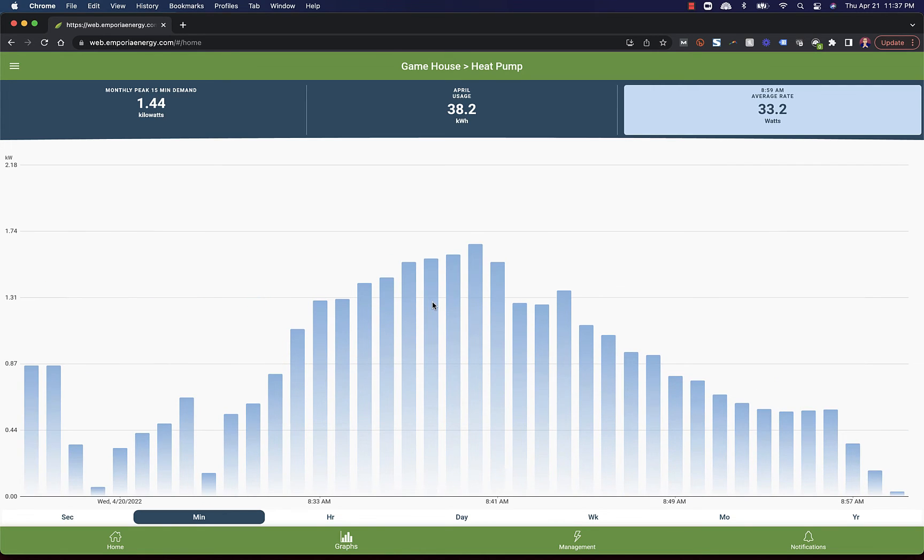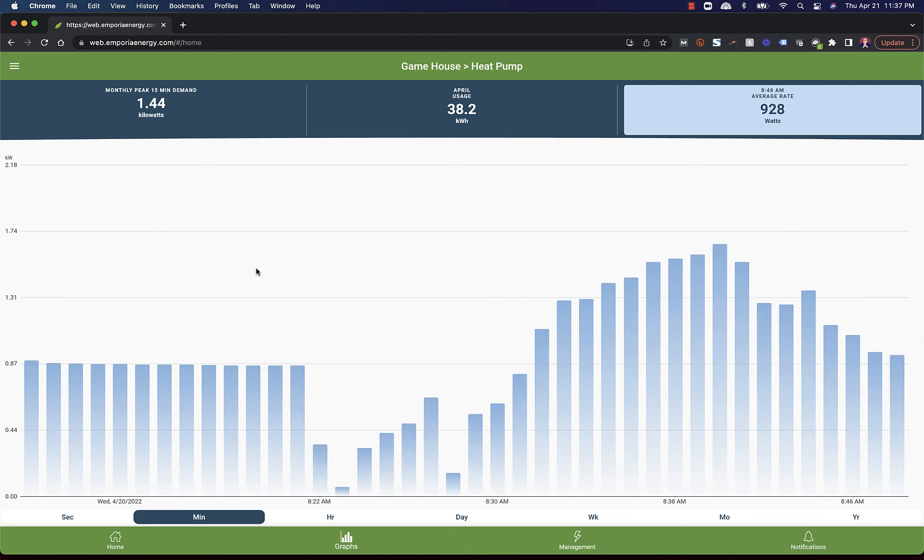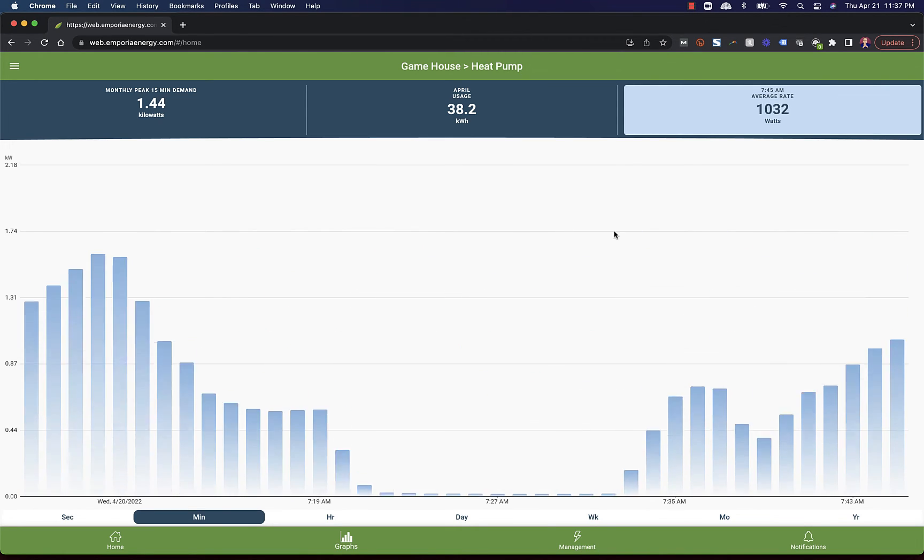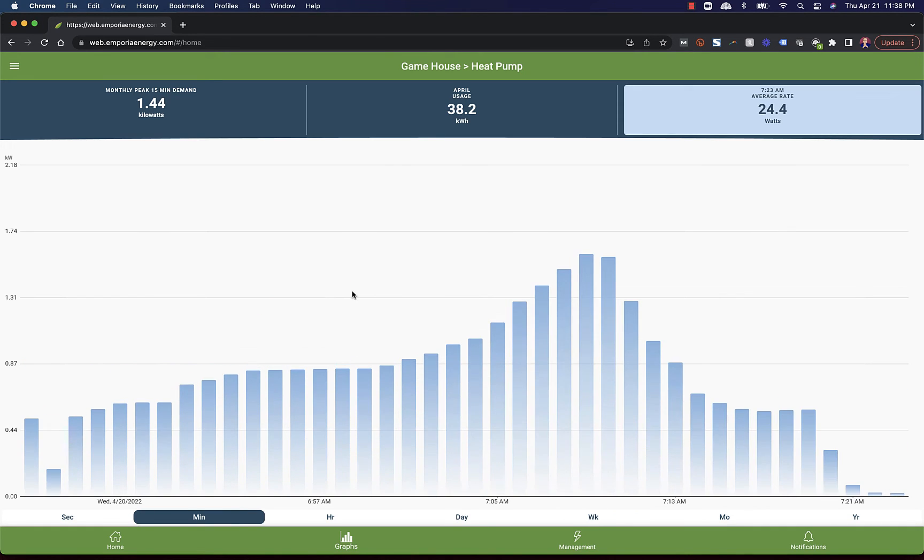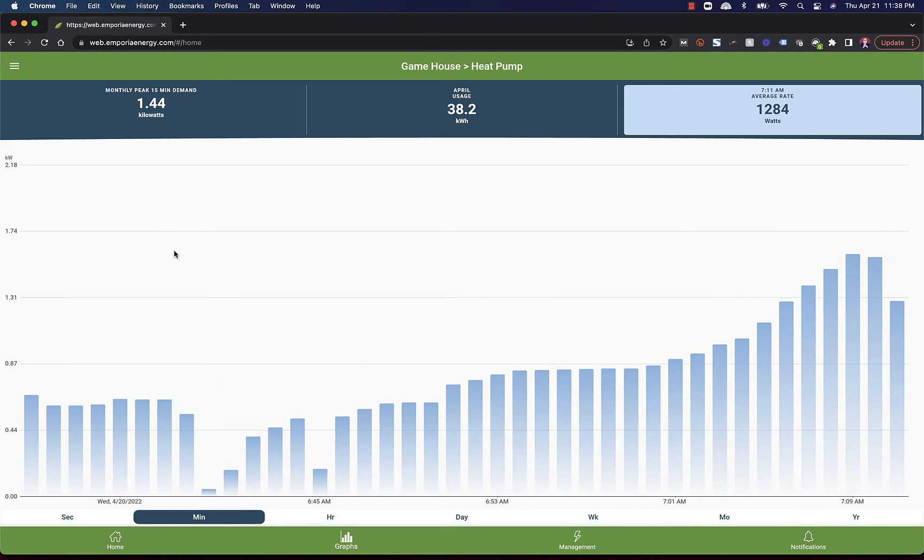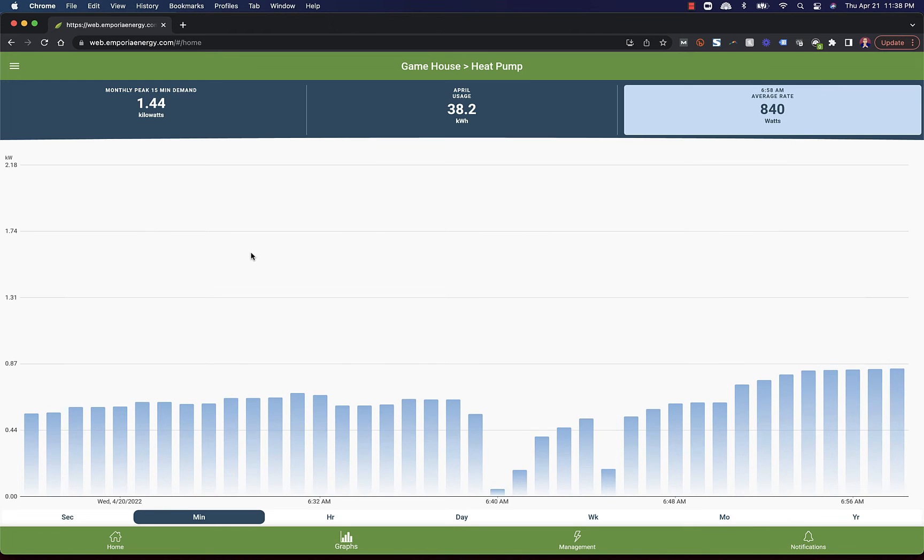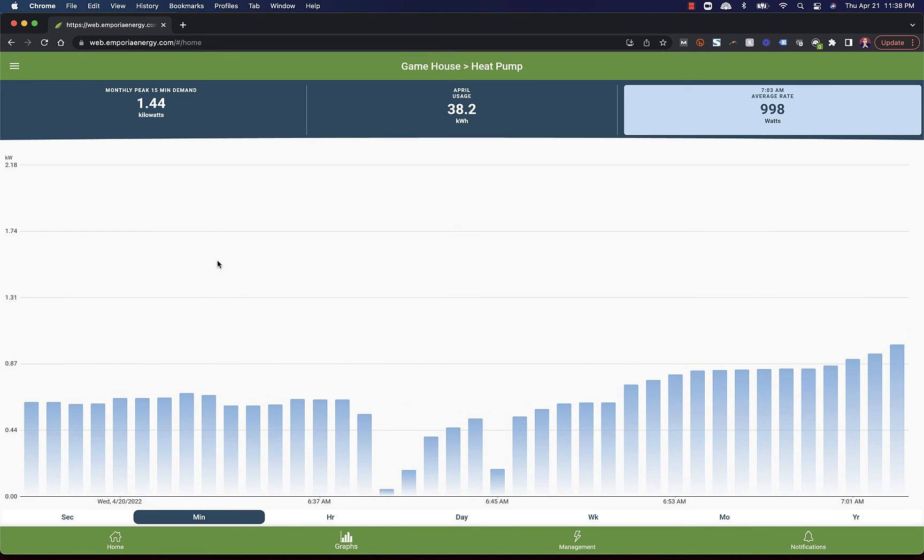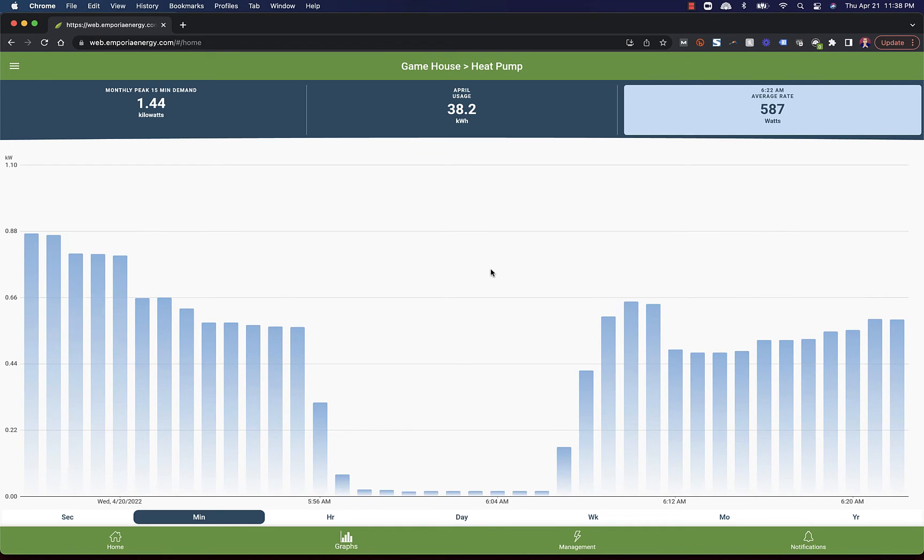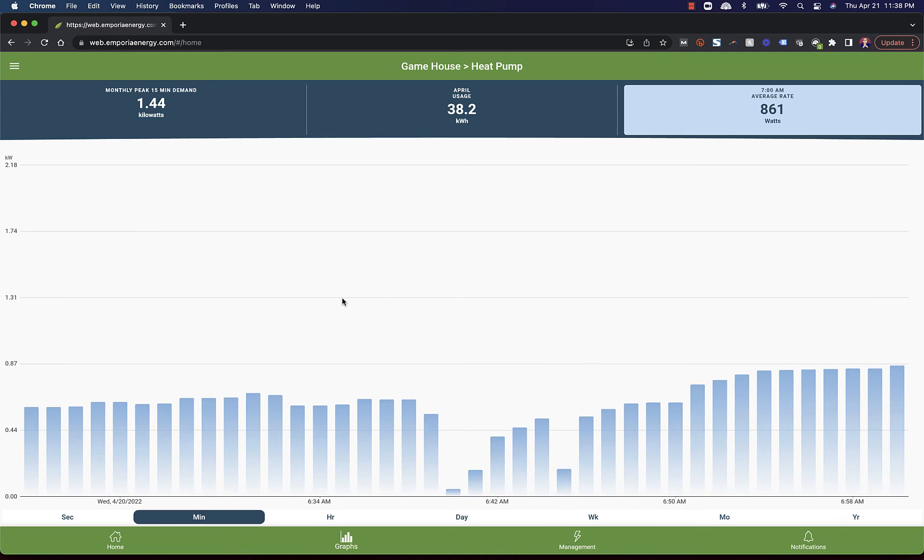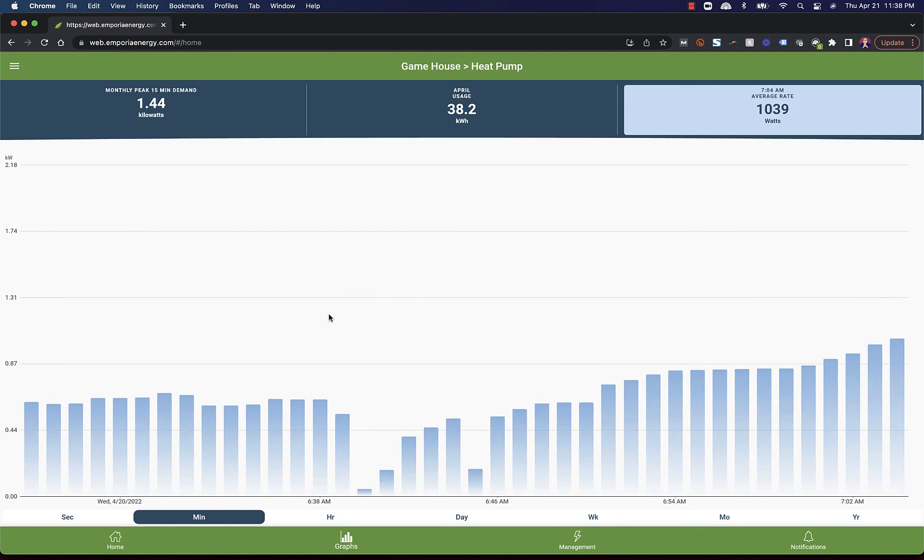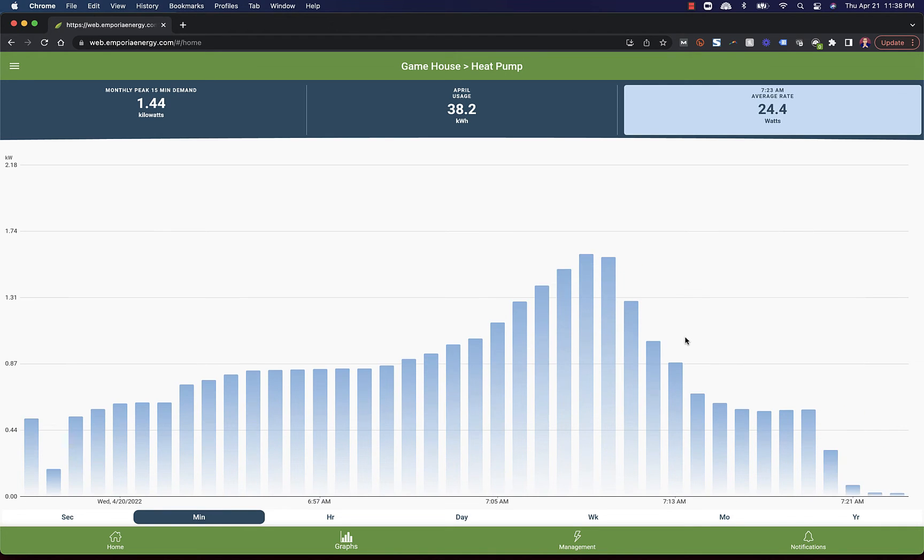Here's another cycle. And oh, you know what? There were a couple cycles here where it ramped way up. So it must not have been happy with how fast it was moving the house. So I mean, all these cycles are pretty long. These are all solid half an hour cycles. If you time a single stage system, it may only run for 5, 10, 20 minutes before it shuts off. I mean, look at this cycle here. Look how long it was running. So it turned on at 6:05 a.m. And it kind of turned off there. That was probably, this is probably a defrost cycle right here.